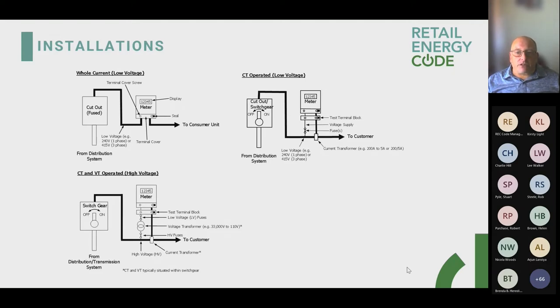In effect, if you've got a 200 amp incoming supply to your customer and you're only measuring 5 amps, you've got a ratio of 40 to 1. That's what we do within the meter. So if the meter was measuring 5 amps, we know the supply should be 200, because it's at 200 to 5, we times it by 40. That's what we do with the readings. So if it's 400 to 5, 600 to 5, we're still measuring based on ratios.